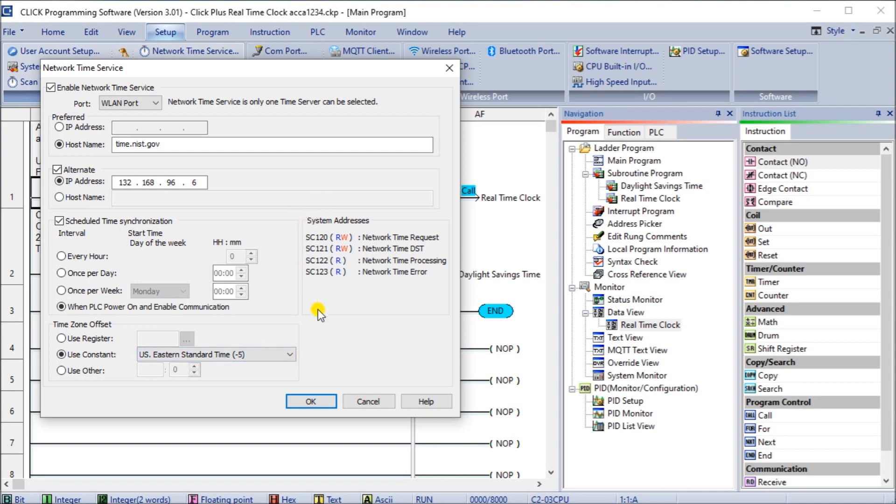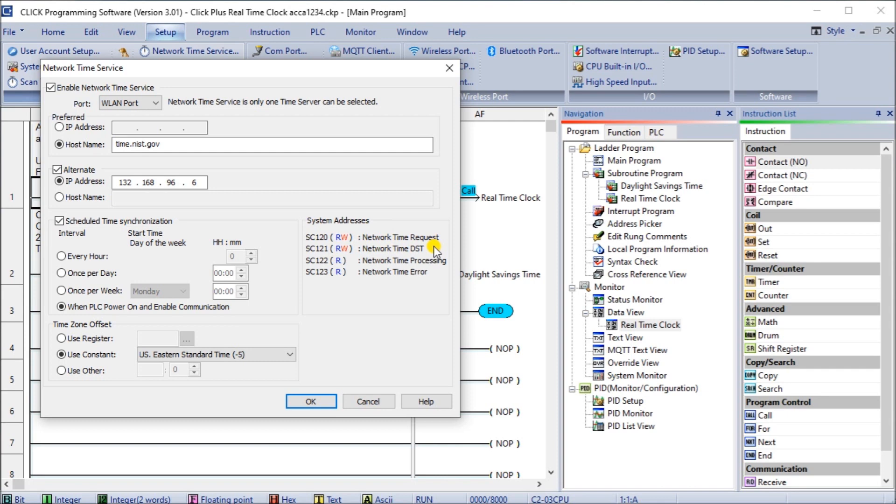Then we also have our system addresses here. We have SC120 which is a network time request, so we can actually request to go out and update the time right now. We also have our SC121 which is network time DST or daylight savings time, so when this is energized we add an hour, when it is off or reset we keep at the same time.